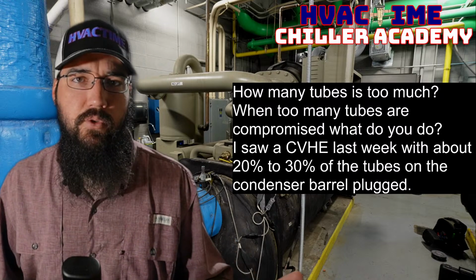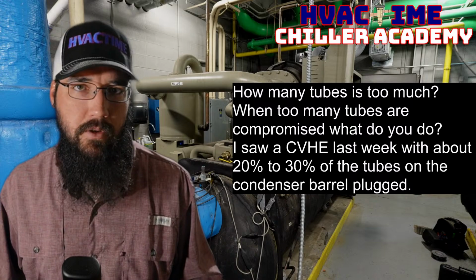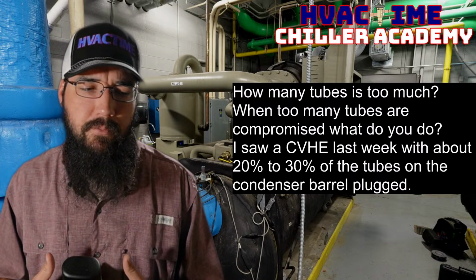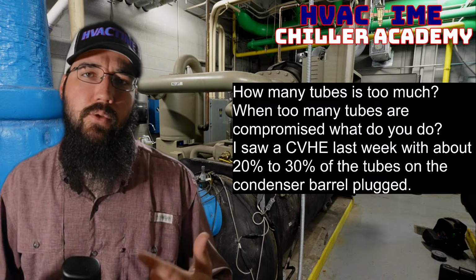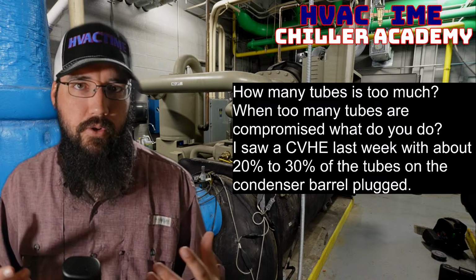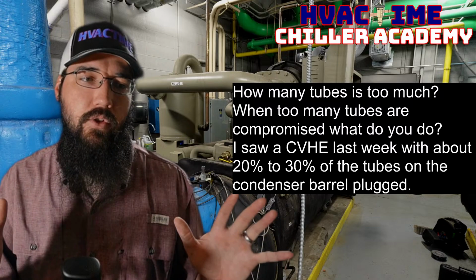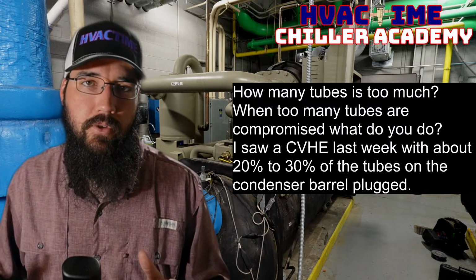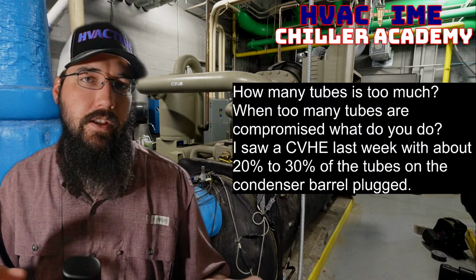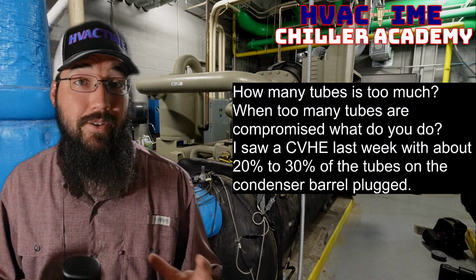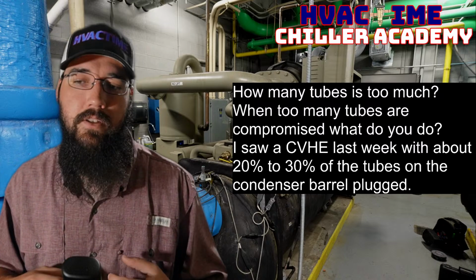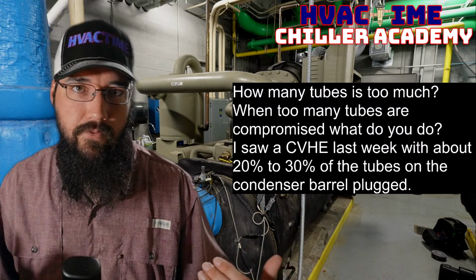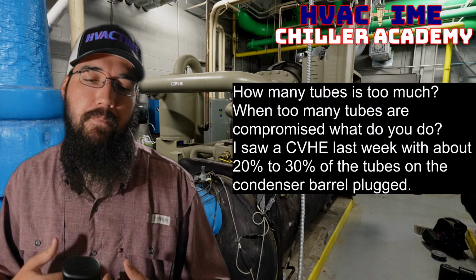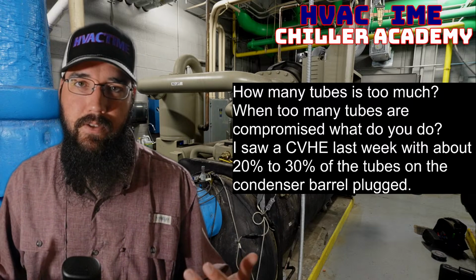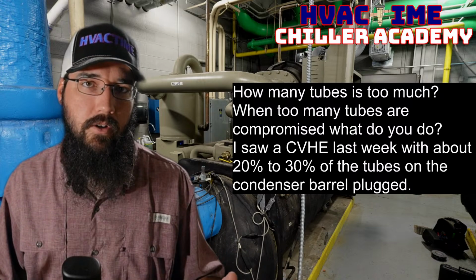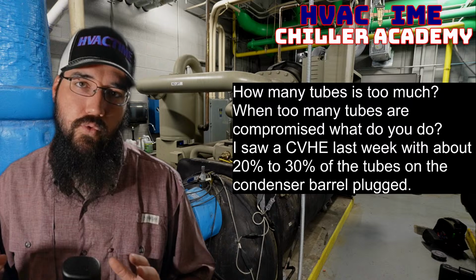The first few tubes you do, you're probably not going to notice much of a difference. And in fact, I'm pretty sure the manufacturers take into account some kind of failure percentage. And so as long as you don't lose X number of tubes, if there's a noticeable difference, it'll be a very minor efficiency loss, but it won't be a significant operational performance loss, if you will. But by the time you're hitting that 15%, give or take 5% mark for a lot of the machines, you're really going to start noticing it.